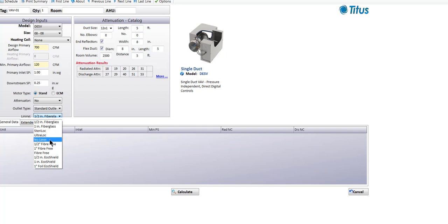The no liner option means no exposed lining materials on the inside of the box, with the assumption that somebody will externally wrap the unit at the job site. There are really two purposes for a liner: thermal protection — helping get heating or cooling where we want it without too much loss to the surrounding environment — and acoustical benefits that vary with liner type. If we go with a no liner option, somebody's going to have to externally wrap that ductwork to avoid thermal losses and condensation on the outside.